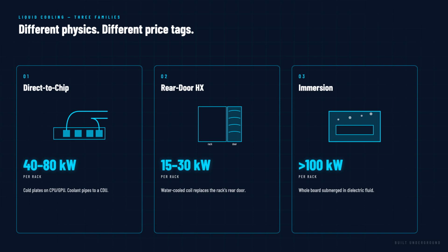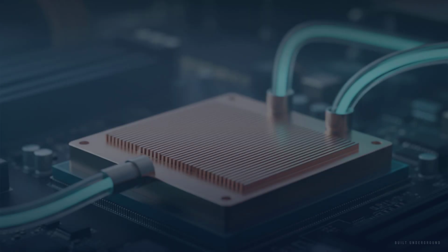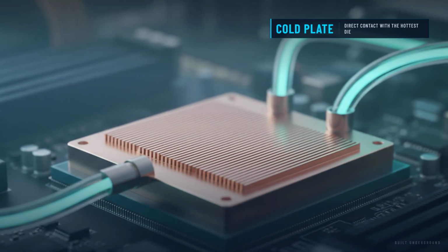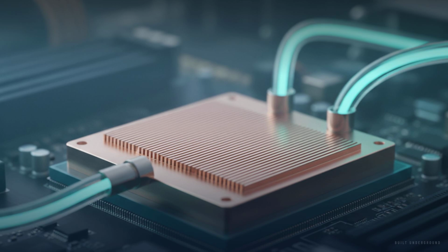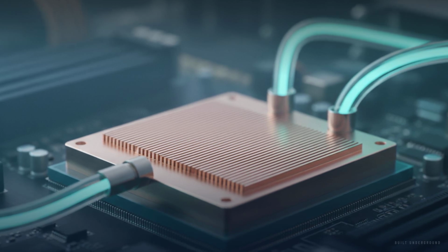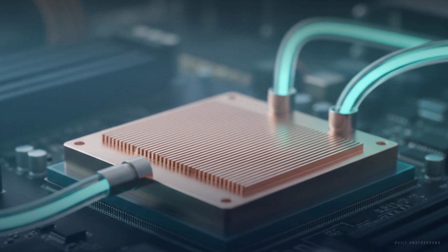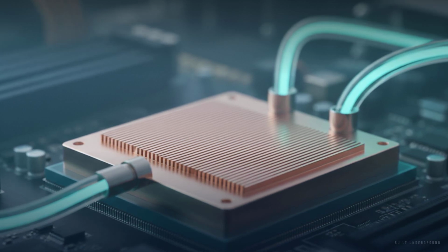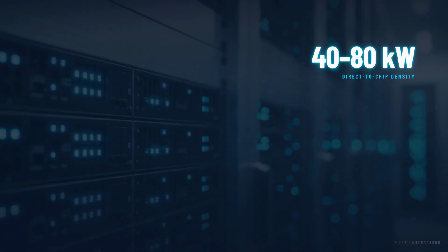Cold plates sit directly on top of the hottest components, the CPUs and GPUs. Coolant, usually water or a water glycol mix, flows through the cold plates, absorbs the heat, and carries it to a coolant distribution unit outside the rack where the heat is transferred to the building's cooling loop. The servers still have some fans for secondary components like memory and storage, but the primary heat producers are handled by liquid. This approach can handle rack densities of 40 to 80 kilowatts comfortably.